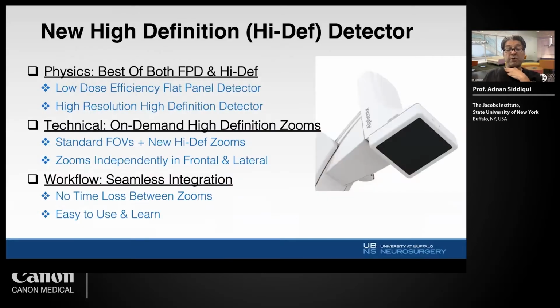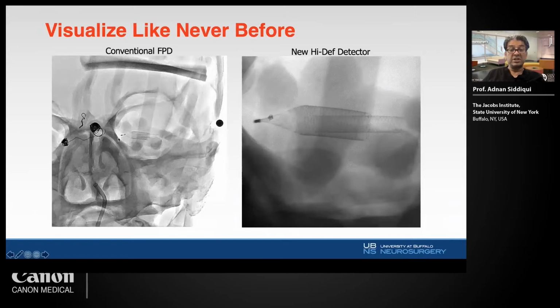And that's what I want to share with you: the value of this system is that there's a smooth transition between the standard flat panel detector down to high def, with standard FOVs compared to the new high def zooms. And really it's just a touch of a button as you mag up or down to zoom in from one or the other. This is an example. This is obviously a phantom, but there you can see two braided devices, and under conventional flat panel versus high def, you can see the kind of detail that you get.